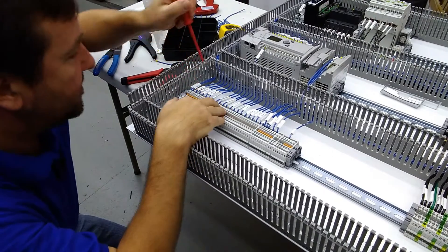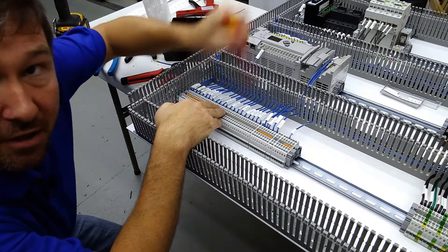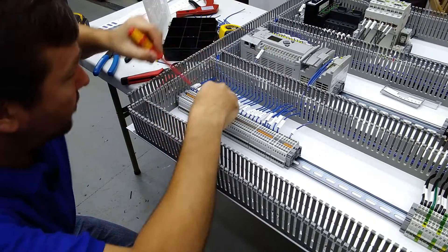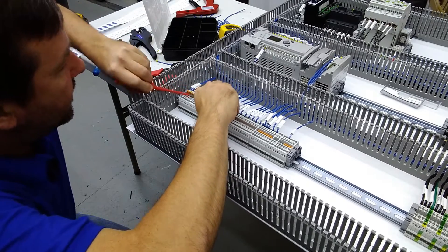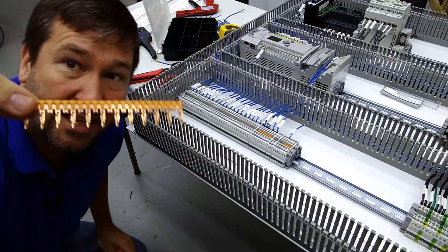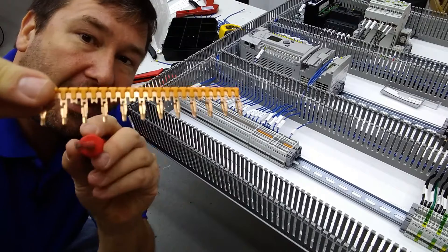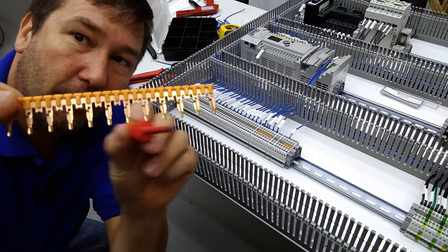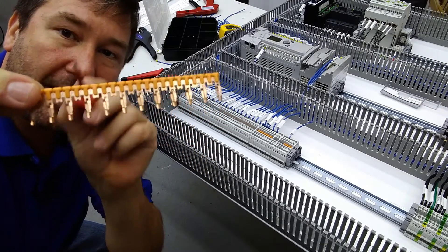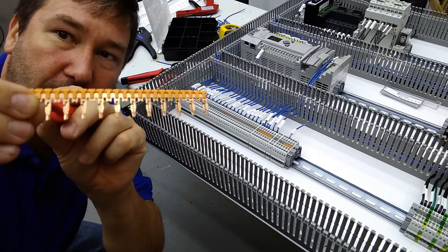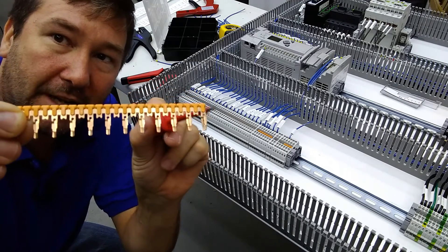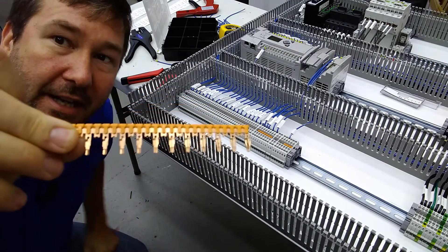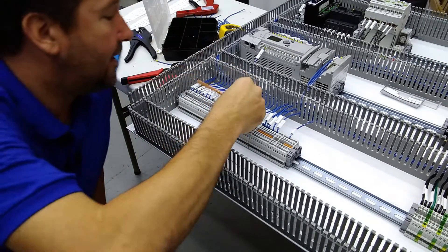And what I've done to do that, instead of having jumpers going across 20 terminals, is I've taken that terminal jumper and I've cut every other one out of it. This way, I only feed 24 volts to the first one and then every other one is powered by that.